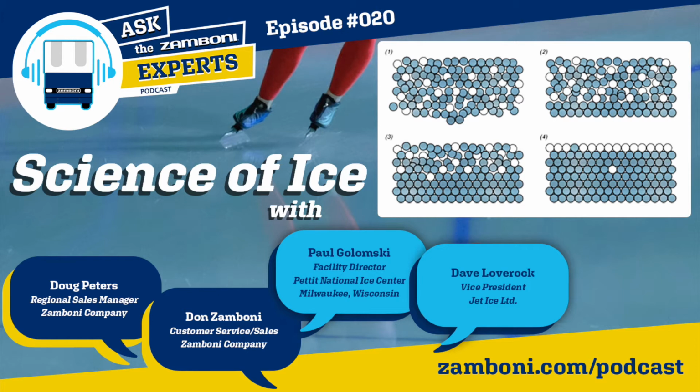Paul, do you have any comments on air in water, or Dave? You don't want to get me started, but yeah, there's a certain degree of interest in dissolved air in water. Really, when you make ice, there's a couple things that you really want to stay away from. You want to stay away from air in the ice, and you want to stay away from mineral content in the water, which, if you remove both of those factors, will give you a harder, denser sheet of ice. The air in ice that you really want to worry about is dissolved air. It's naturally occurring in most waters, and it is unseen. But you want to remove the mineral content, you want to remove the dissolved air when you're making ice.